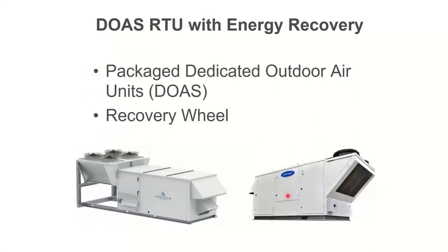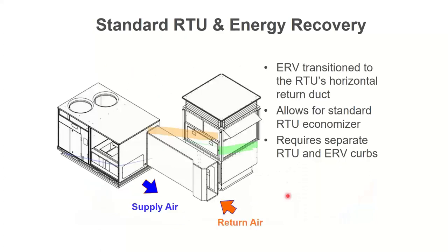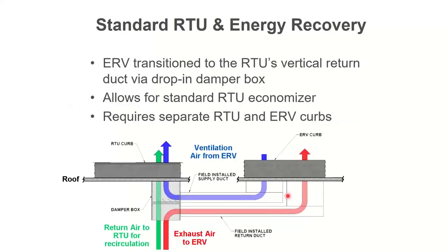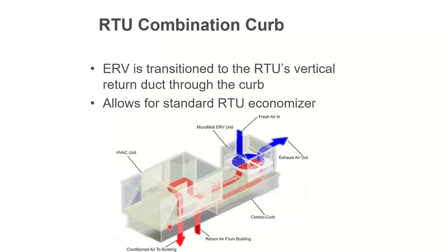You can get ERVs that are built into packaged outdoor units. This is fairly common now. These get paired up with VRF systems very frequently if you need fresh air to come in some way. So that's an option as well. You could take a standard rooftop and an ERV and duct them together on the roof. You could take a standard rooftop and an ERV and duct them together under the roof. You can get a combination curb.